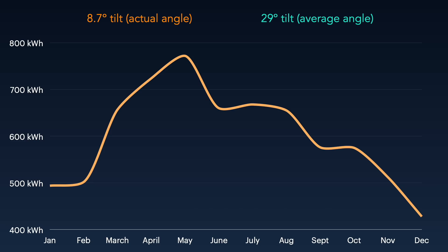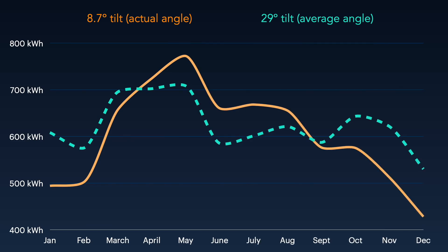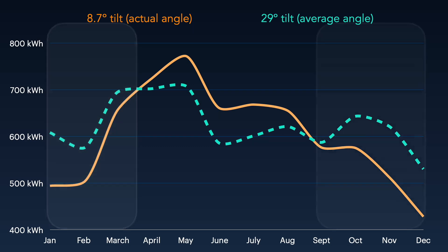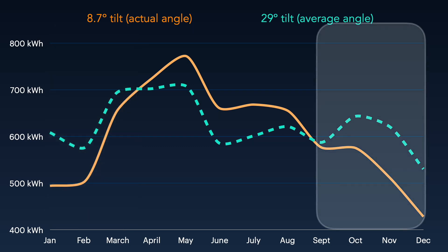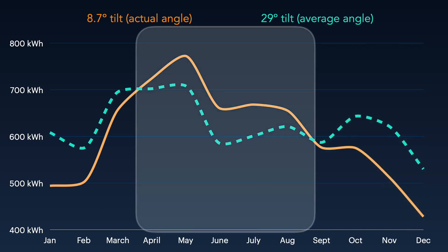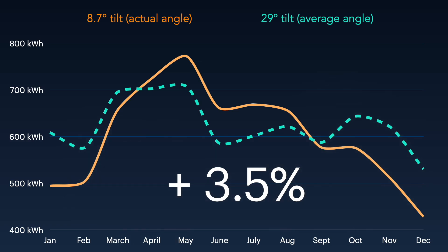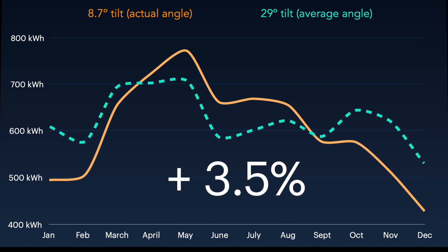The orange line is based on the actual angle that my panels are at and this blue line is the prediction if I change the angle of the panel to the 29 degree tilt. In the early months of the year the 29 degree angle would produce more power. It would also produce more power in the last few months of the year but from April to August my existing angle does better. Averaged out over the whole year I would gain 3.5 percent by changing the angle to the 29 degree tilt.